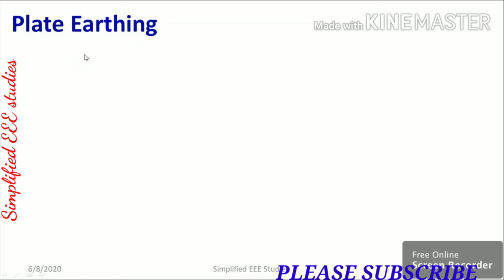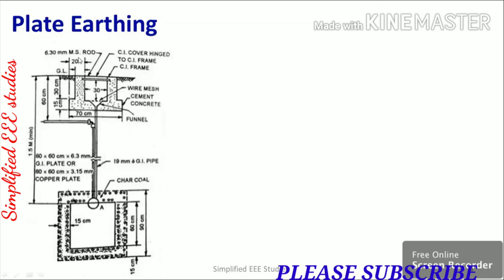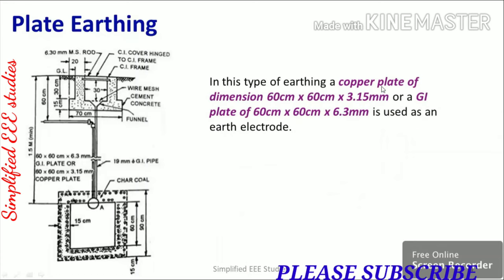Now let us move on to plate earthing. In this type of earthing, if you are using a copper plate, the dimension must be 60 cm × 60 cm × 3.15 mm. If you are using a GI plate, the dimension must be 60 cm × 60 cm × 6.3 mm. That dimension has to be maintained accordingly.